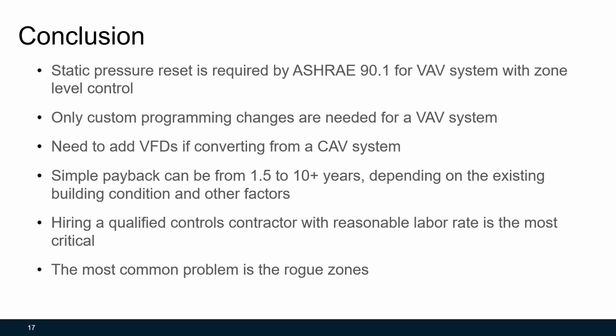The most common problem implementing static pressure reset is rogue zones. Rogue zones are zones with VAV dampers always at the maximum damper position. This could be due to a design error, or it could be due to a sensor error. These rogue zones need to be fixed or ignored for this control strategy to be effective.